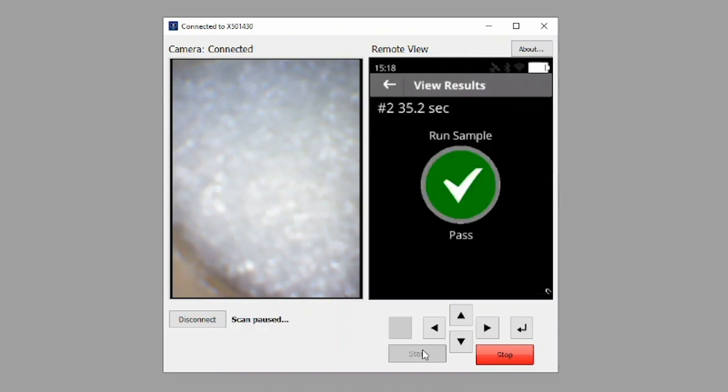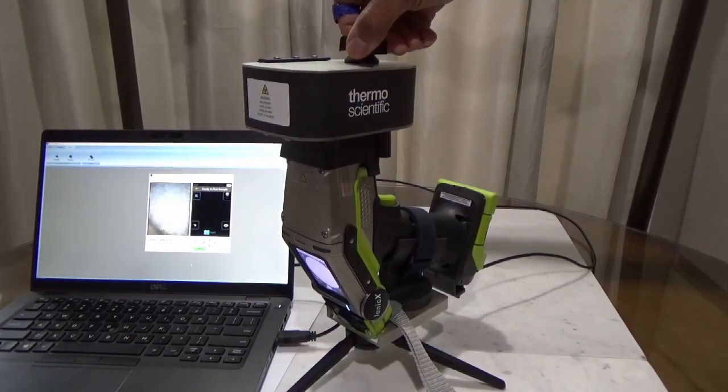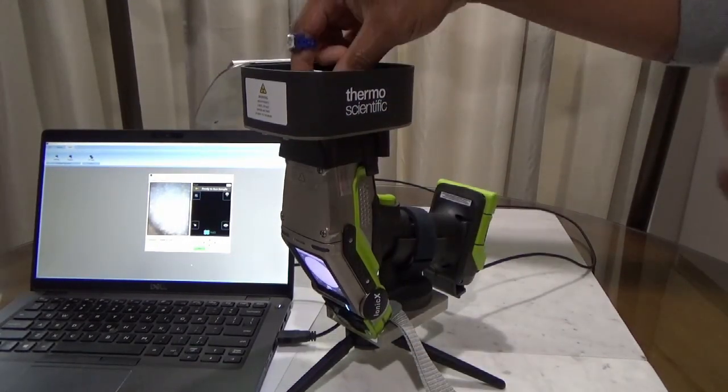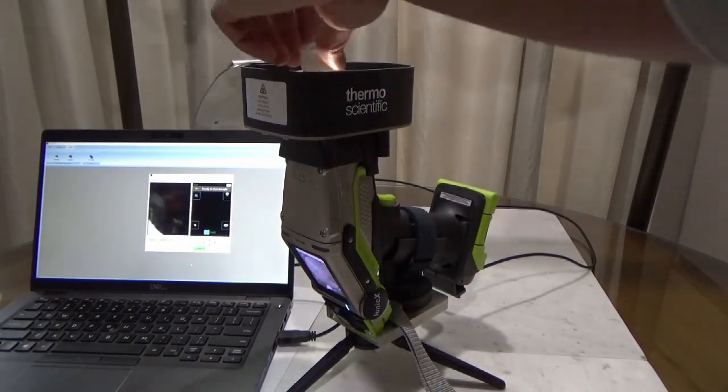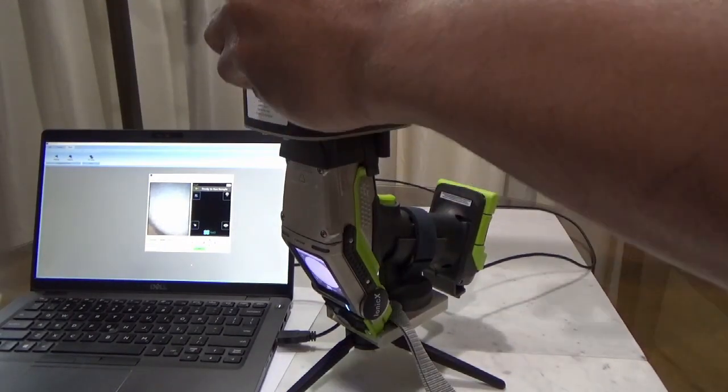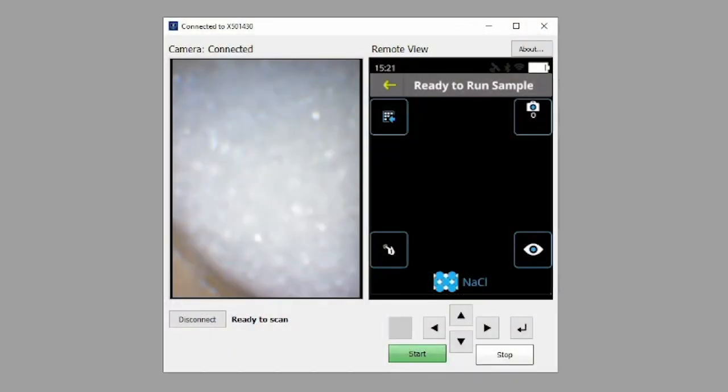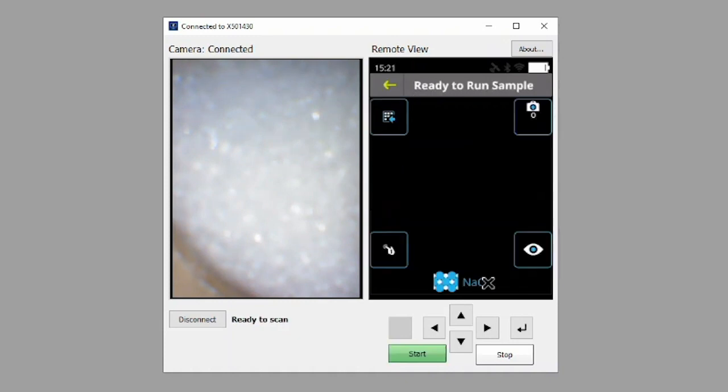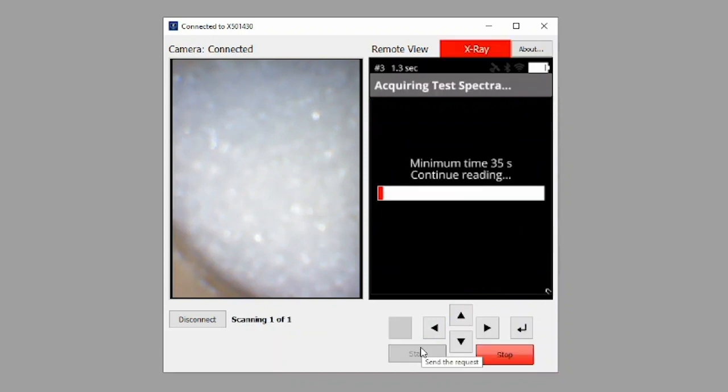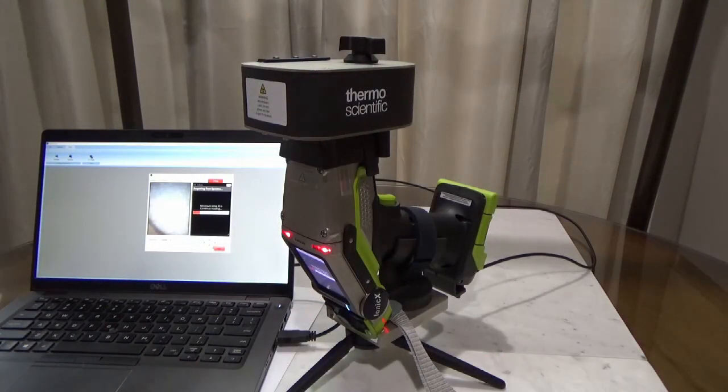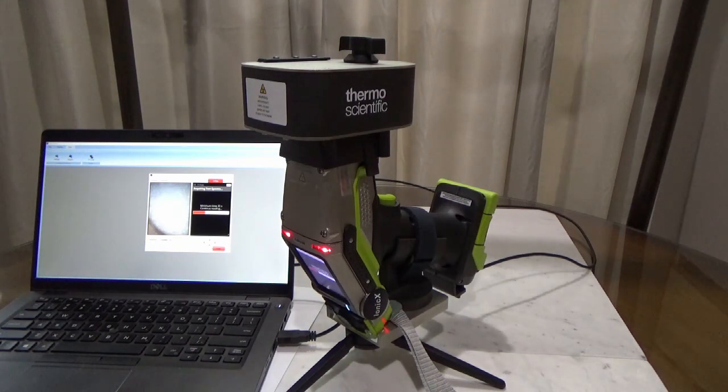Here we see a pass result for sodium chloride. Click the back arrow at the top of the screen, and let's run a second sample of sodium chloride. Open the top of the sample compartment and replace the sample with the next one. Securely close and lock the lid. Click the top left icon to check that the sample counter has increased by 1. Click the green Start icon to begin the analysis. Note that any time there are x-rays emitted, the instrument will first make an audible sound cue that analysis has begun, and it will also display red indication lights for the duration of the emission.